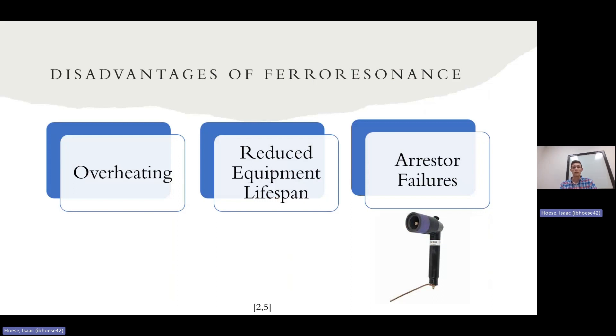Other small disadvantages are flicker, charring of paint was an interesting one, and loud noise. Transformers have actually been known to start shaking violently when they're under a ferroresonance state.